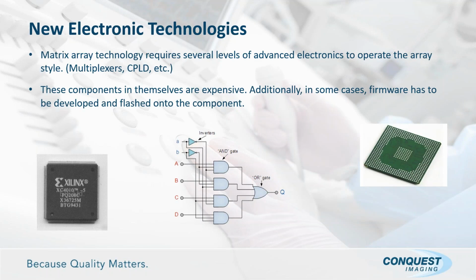Now, I mentioned a little bit earlier, a lot of probes nowadays are what we call matrix array technology. And these are all multiplexed. They all use components like CPLD, etc. Some of them have firmware in them. There's flash, software flashed on the components, etc. So again, you stop and think about it. If you've got to flash a component, for instance, put some software on it, you've got a software developer involved to create the software. Then you're working with an electronics engineer to make sure that they've got the right component. They've got to design the process to get that flashed in, both from a manufacturing standpoint as well as the initial design. Then there's the issue of how it mounts to the board, et cetera, et cetera. So there's just several levels, even on the electronics, that you have to go through to make these things work properly.